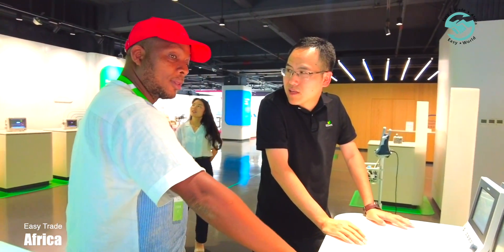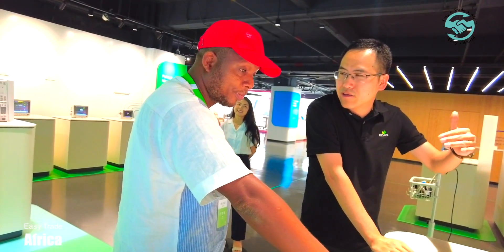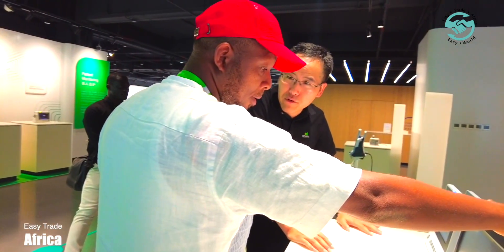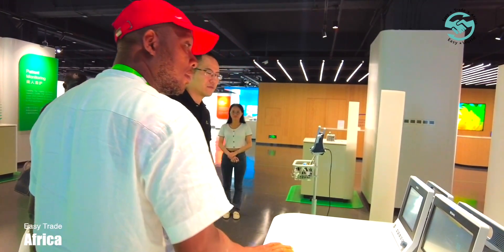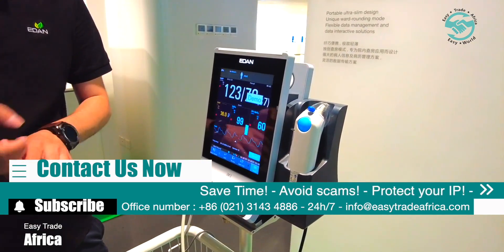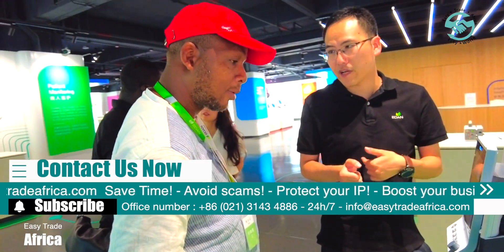It's suitable for those who need a very high-end machine for the ICU or recovery room. Normally configured with SpO2 and IBP, with temperature as optional — maximum three parameters. This is for spot check, while the patient monitor is for continuous monitoring. The vital signs monitor is for spot check, useful in emergency scenarios.